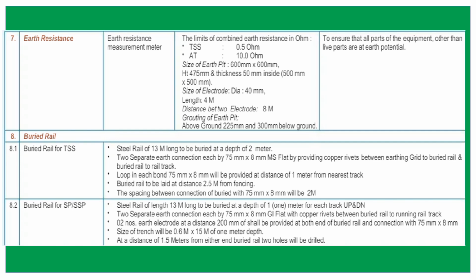And the lightning arrestor, auxiliary transformer, control room cubicle, all these things have individual earth cone, and its value is not more than 10 ohm, but the combined means all are interconnected. With the combined of all earthing arrangement, its reading must be 0.5 ohm or below, not more than 0.5 ohm. And size of the earth, everything has been given. Earth cone length is 4 meter, diameter is 40 millimeter, distance between two earth electrodes is 8 meter. These are all things for the earthing arrangement.